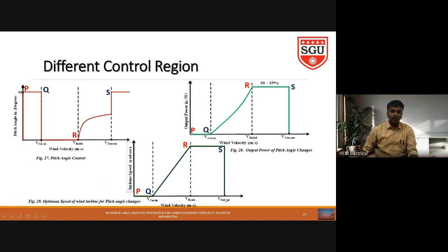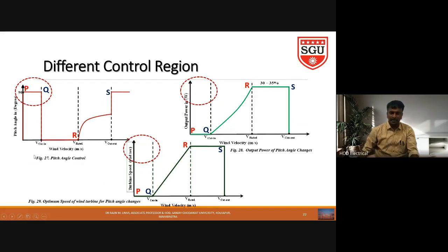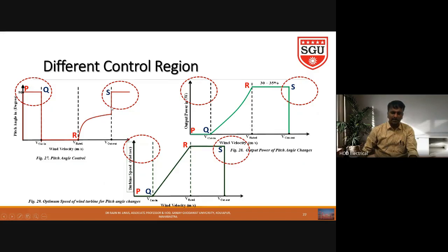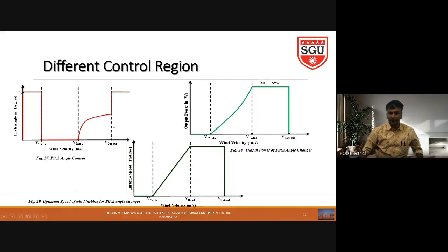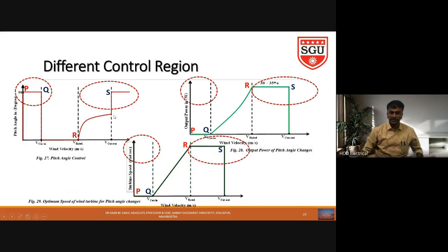At point S, turbine speed also comes down to zero. To summarize, pitch angle control is applied in the region from 0 to V_cut-in (pitch angle = 90°) and in the region above rated wind speed (pitch angle gradually increases from 0° to 90°). In the region between V_cut-in and V_rated, pitch angle is held at 0 degrees and other control strategies like MPPT apply.